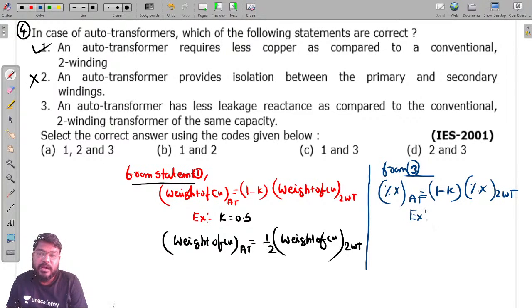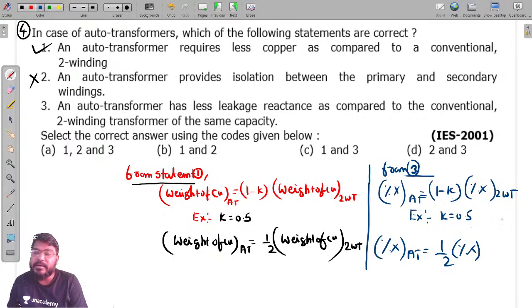For example, assume k is equal to 0.5. Now substituting k here, what do we get? Percentage reactance of auto transformer is equal to 1/2 times of the percentage reactance of the two winding transformer. This is also 50%. So now statement 3 is also correct - percentage is less value as compared to the two winding transformer.